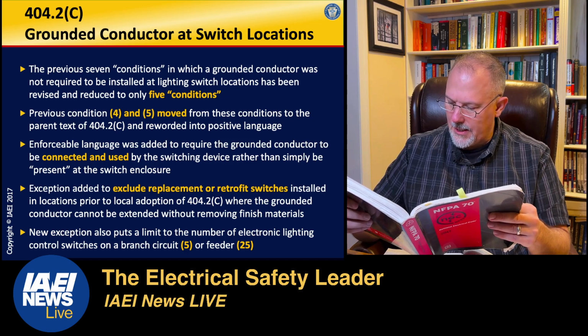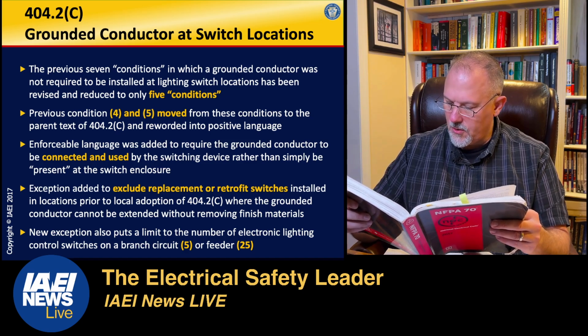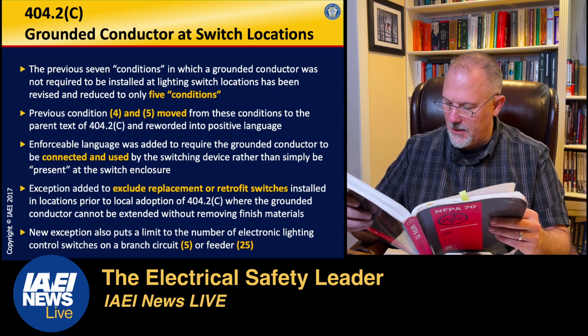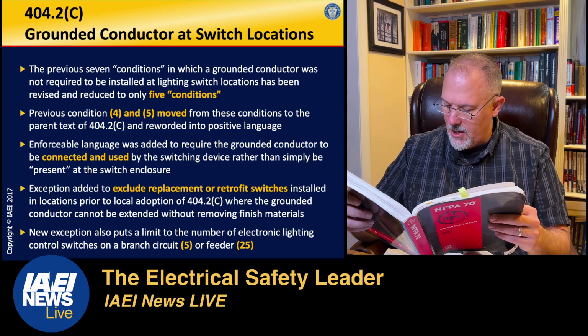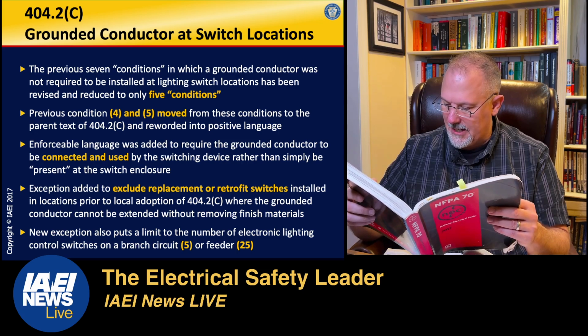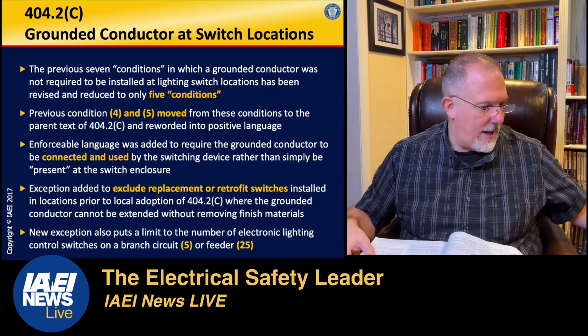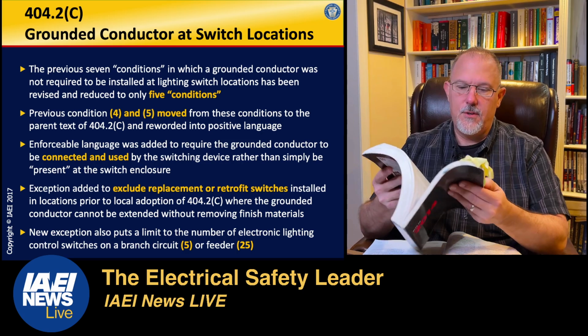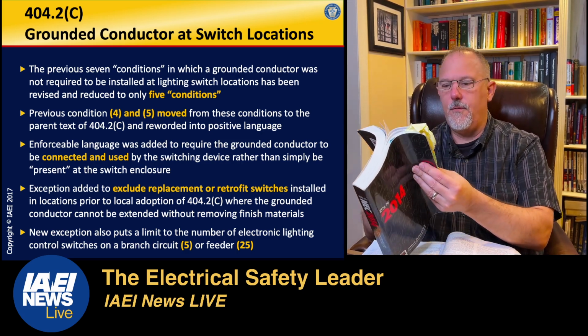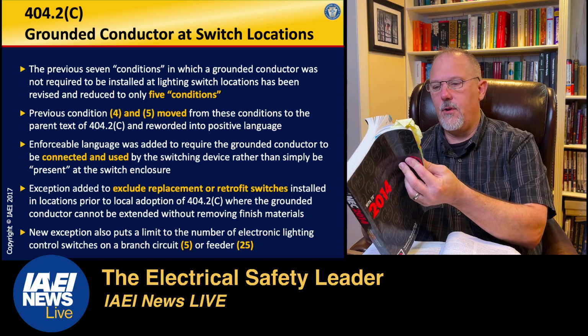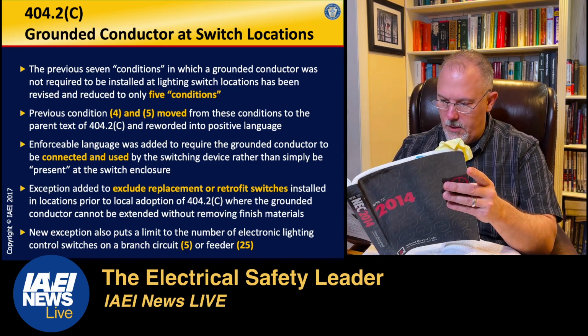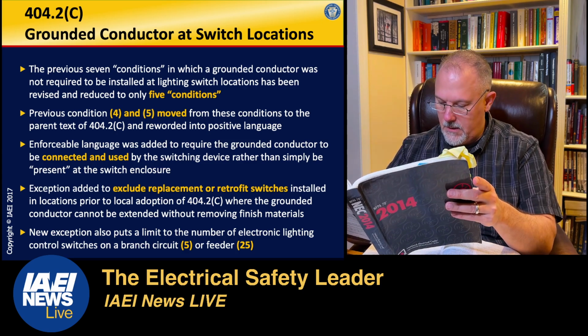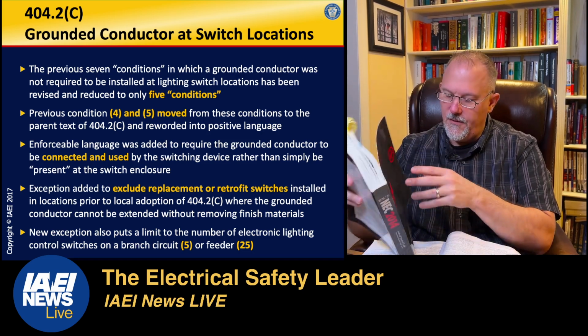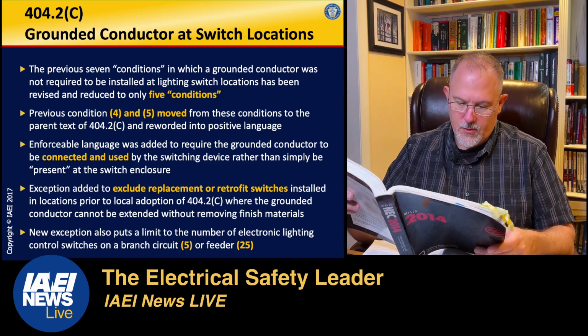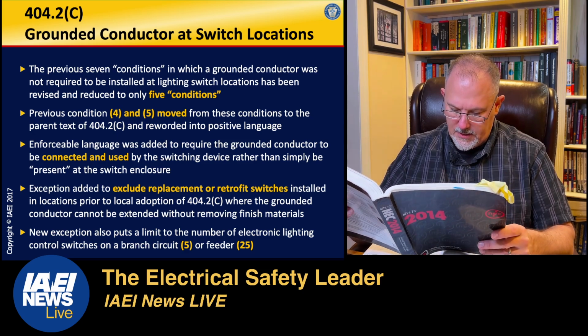Electronic lighting control switches. Electronic lighting control switches shall be listed. Electronic lighting control switches shall not introduce current on the equipment grounding conductor during the normal operation. The requirement to not introduce current in the equipment grounding conductor shall take effect on January 1st, 2020. Let's look at the 14 code at 404.22. Oh boy, 404.22 did not exist in the 14 code.